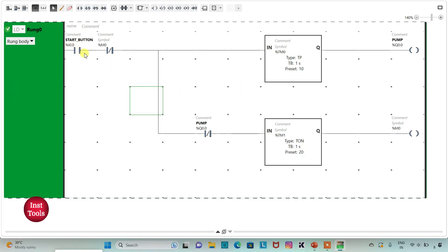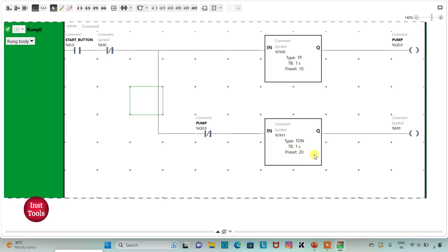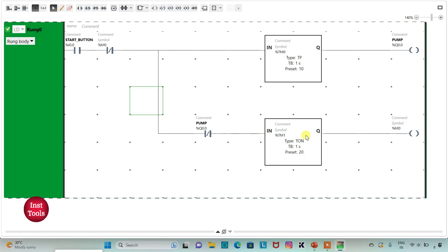So here our ladder diagram is completed. When start button is turned on, pump will be turned on for 10 seconds. And after 10 seconds, pump will get turned off and it will be off for 20 seconds. And after 20 seconds, the pump will get started by its own for 10 seconds. And after 10 seconds, the pump will get turned off for 20 seconds, and this cycle will repeat itself.